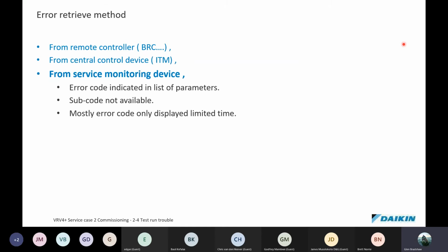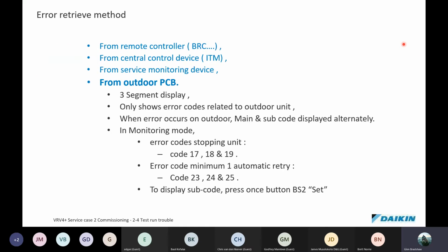From a service monitoring tool, these are the devices we spoke about earlier on: the service checker, the monitoring tool, and the D checker. These give an error code indication and a list of parameters, and the subcodes are not available. Mostly the error code is only displayed for a limited time. In monitoring mode, you can get error codes from the outdoor unit using codes 1, 17, 18, and 19 for error codes that stop the unit, and then error codes for the automatic retries.